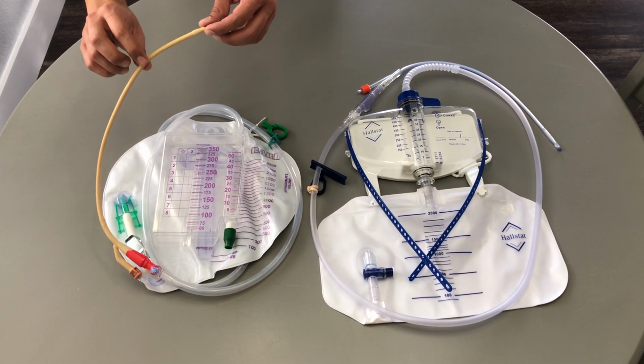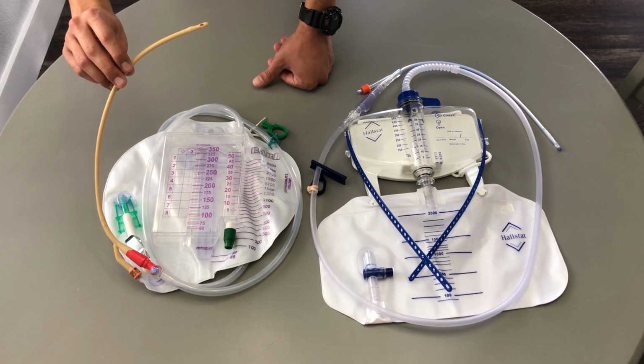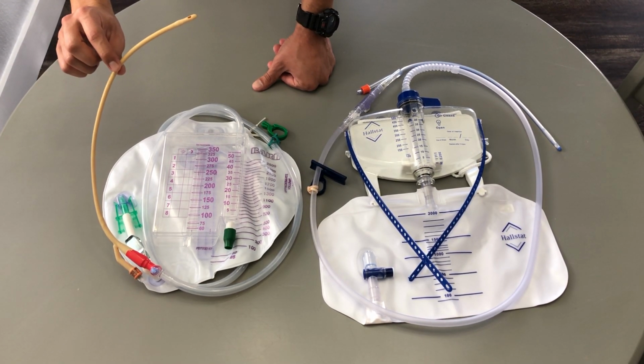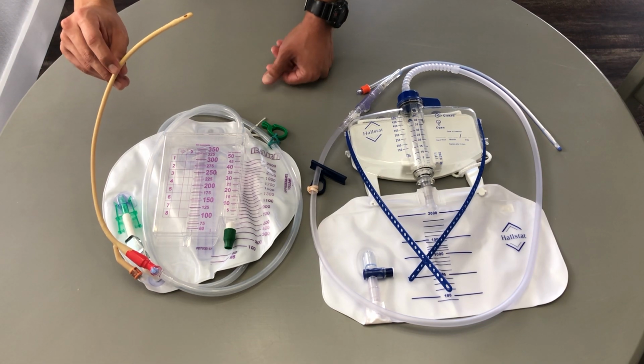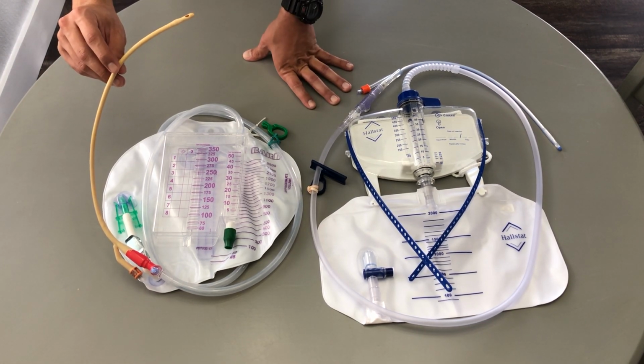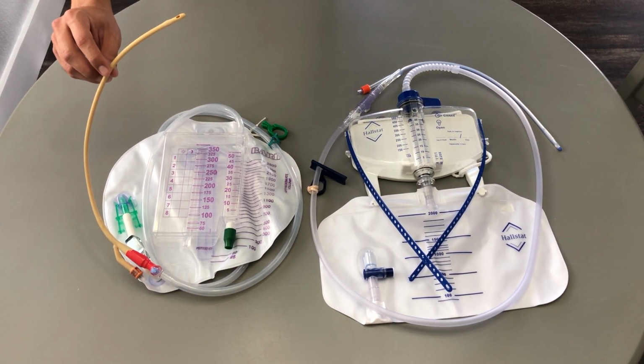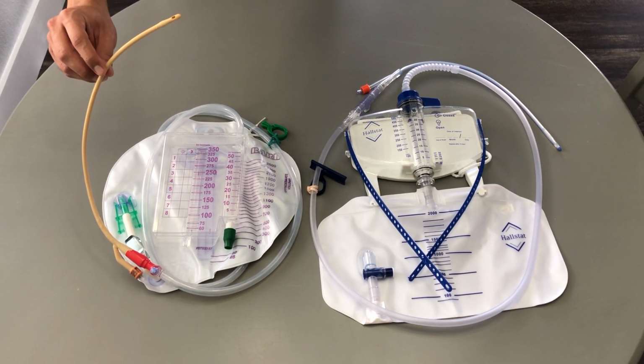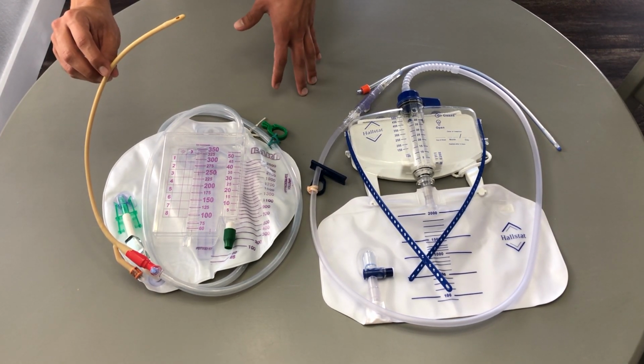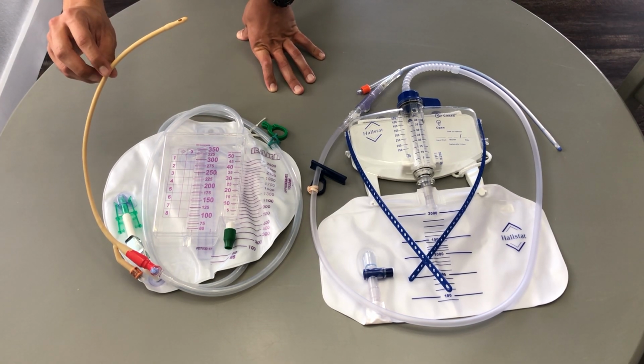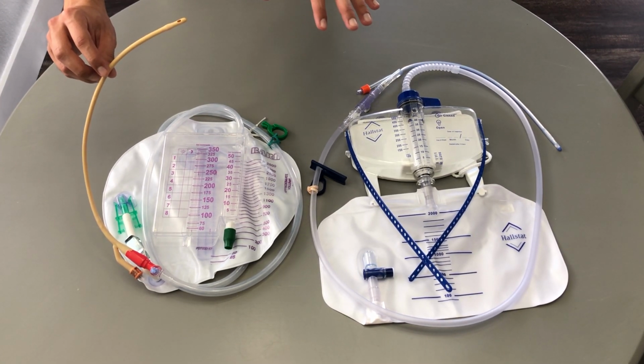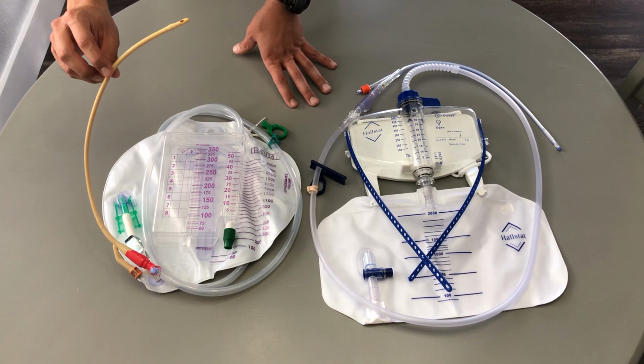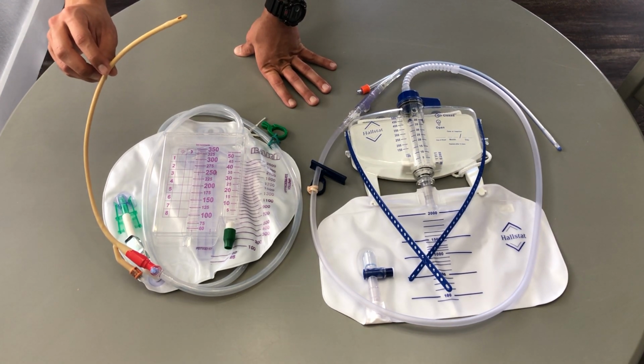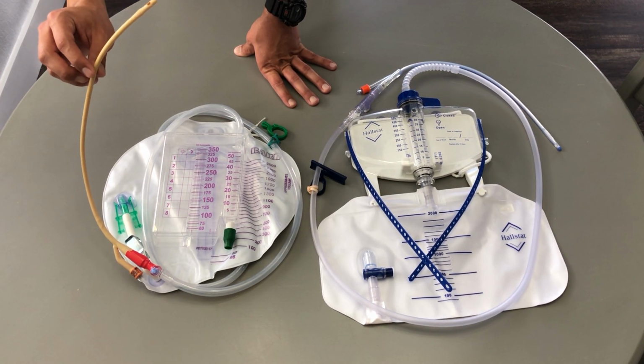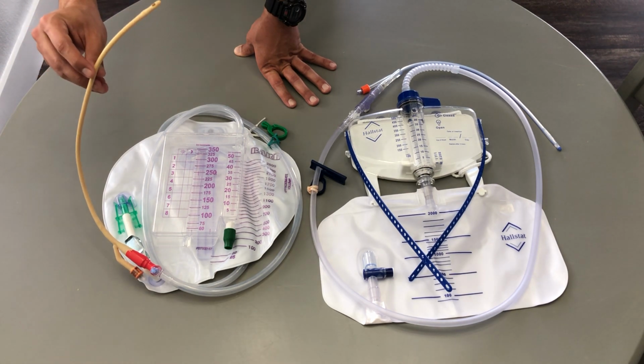You can't see it, but this catheter is actually coated with a very thin antimicrobial coat that consists of small ions of silver. This silver elutes through time and kills bacteria as it passes through, but usually after 7 days, the antimicrobial coat is almost completely gone, and by 14 to 15 days, you'll have almost no coverage or antimicrobial coat on this catheter.